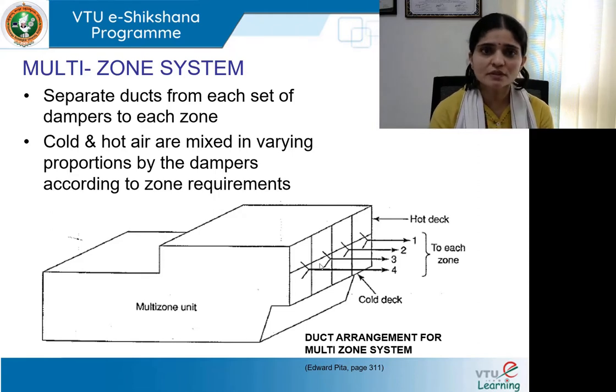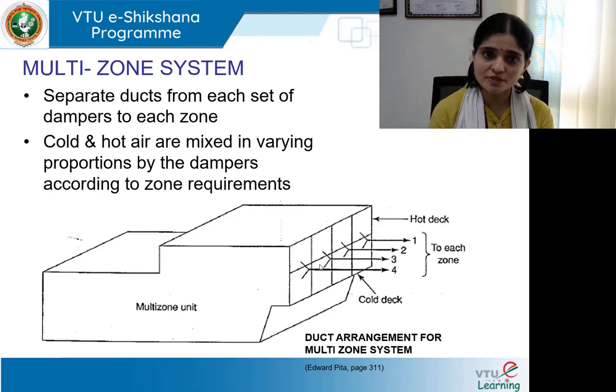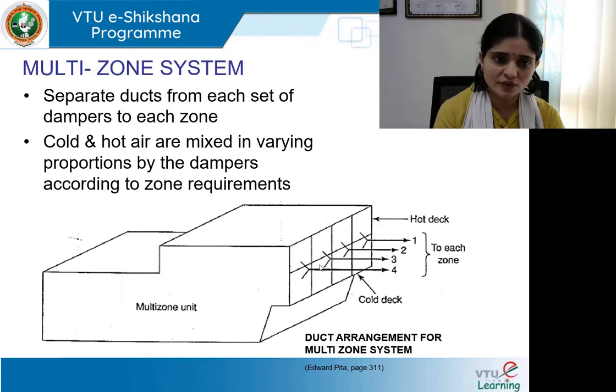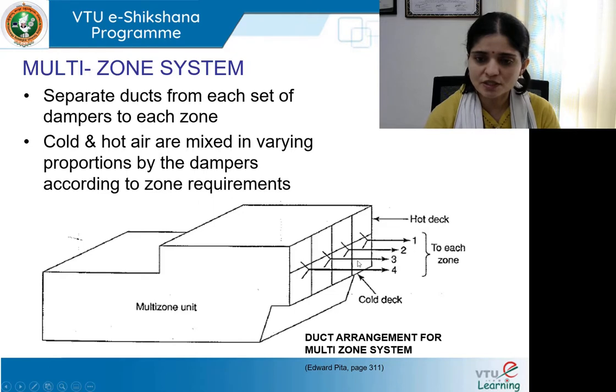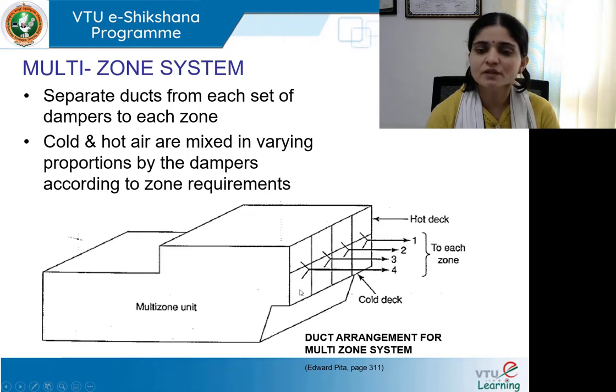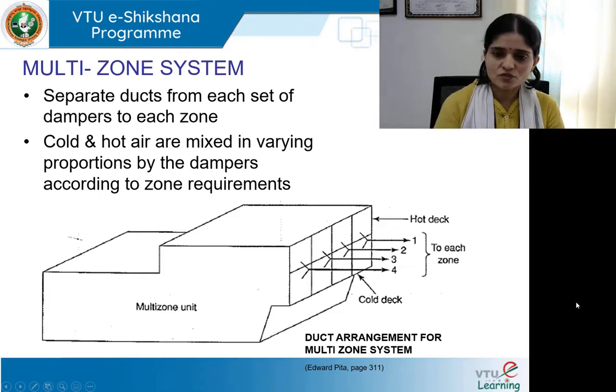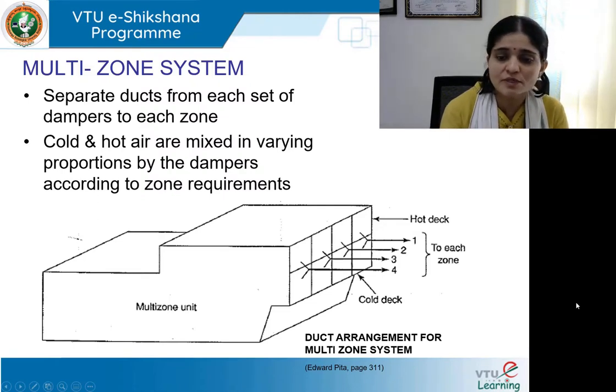Cold and hot air are mixed in varying proportions by the dampers according to zone requirements — the proportion can be calibrated as per zone demand. Ducts branch out from the hot deck on top and cold deck on the bottom. A duct branches from the hot deck and another from the cold deck; they then move to the individual zone. The damper at the interface controls the airflow merging into each zone.